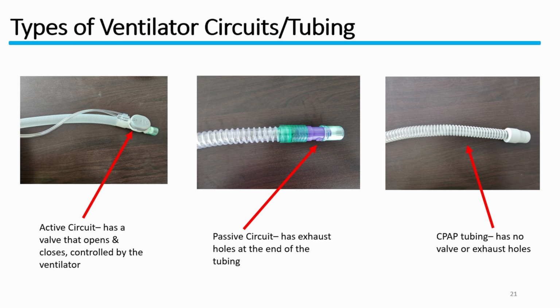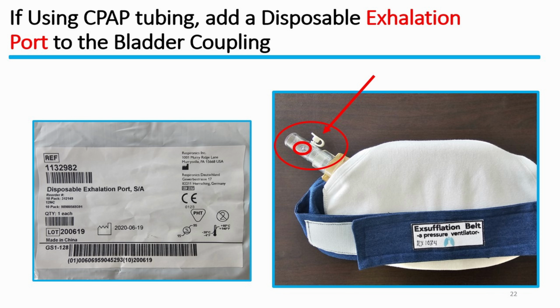On the right is plain CPAP tubing. CPAP tubing does not have an exhalation valve or any exhaust holes because the tubing is usually connected to a mask that has exhaust holes. CPAP tubing works well with the exsufflation belt because it is durable and very inexpensive, but there's no place for the air to escape between breaths. If using CPAP tubing, add a disposable exhalation port to the bladder coupling.